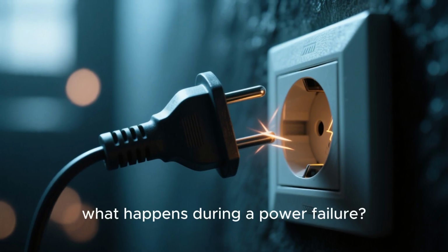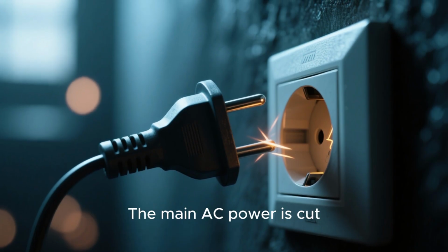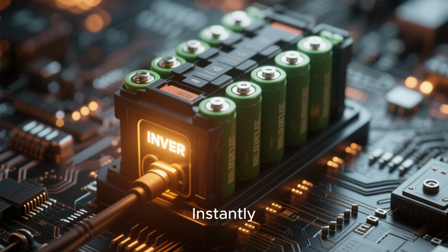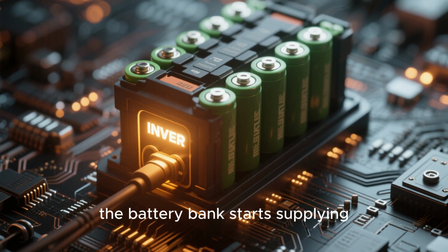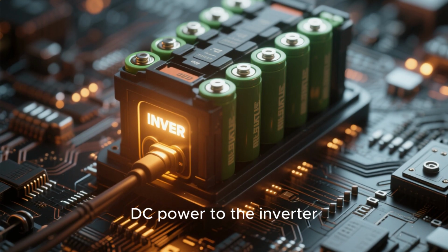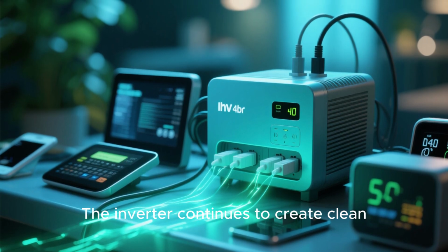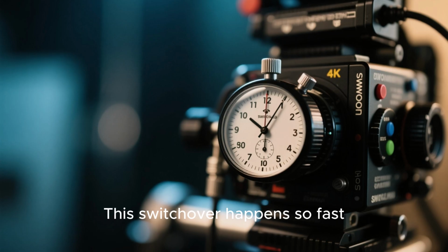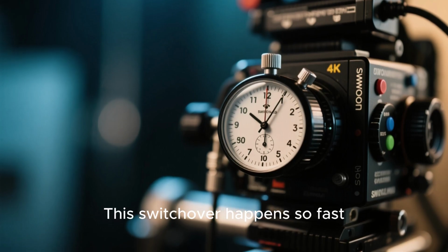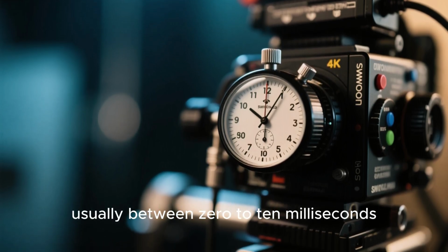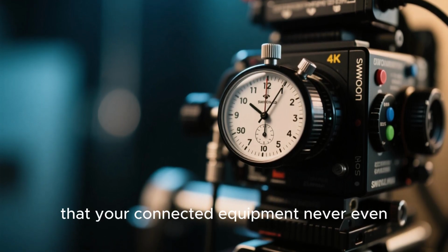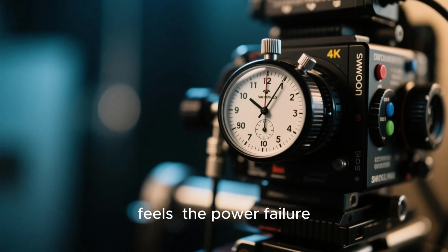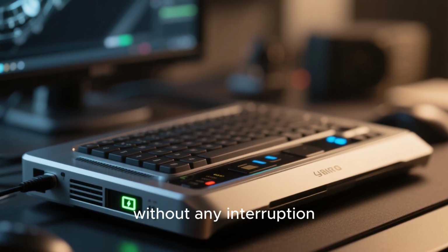Now, what happens during a power failure? The main AC power is cut. Instantly, the battery bank starts supplying DC power to the inverter. The inverter continues to create clean AC power for your load. This switchover happens so fast, usually between 0 to 10 milliseconds, that your connected equipment never even feels the power failure. It just keeps running without any interruption.